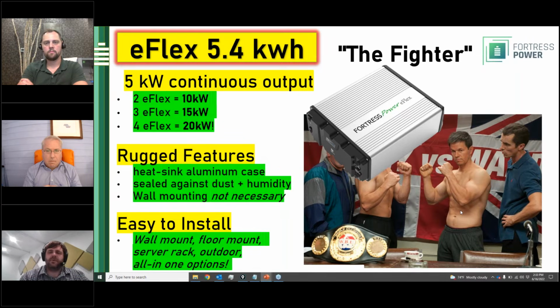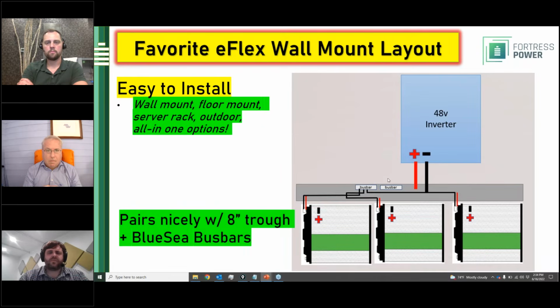That's a bit simpler of a setup than your standard 5 kilowatt hour battery. This is my favorite layout for the eFlex. You put it on the wall, position the terminals so you can go straight up into the trough via cord grips, put a bus bar into that trough, and then go straight up into the 48 volt inverter. As long as you have a hydraulic punch, some bus bars, and an 8-inch trough, you can have a very neat and clean installation with good cable management, all on the wall.